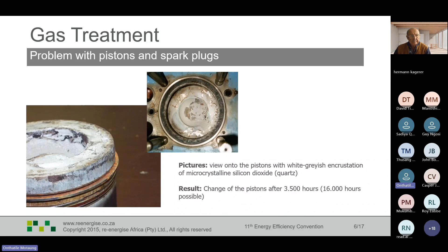So you can see now the deposit on the cylinder head. This deposit requires that you change the pistons quicker - you can see 3,500 hours compared to 16,000 hours. This is a problem because each downtime like this means you lose valuable production if you're not treating your gas.